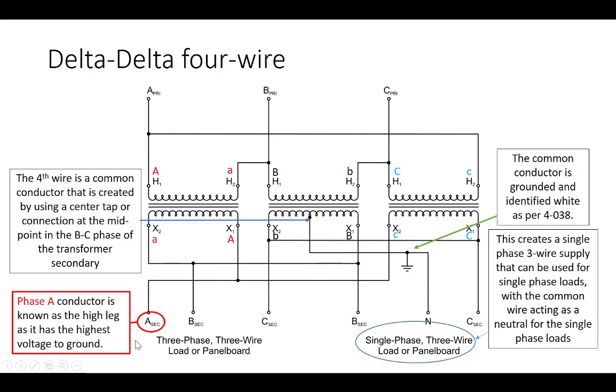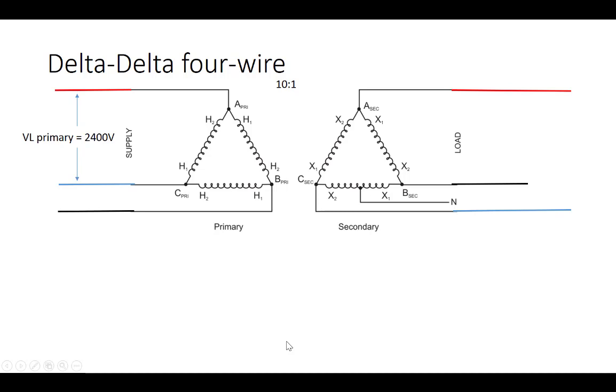And in delta 4-wire systems, the phase A conductor is always the one with the highest voltage to ground. Code requires us to have the tap made in the B to C phase, and that the high leg is always going to be the phase A conductor. And most of the voltages that we have with a delta 4-wire system are pretty straightforward to calculate. So I will just go through the voltages and give you the answers.